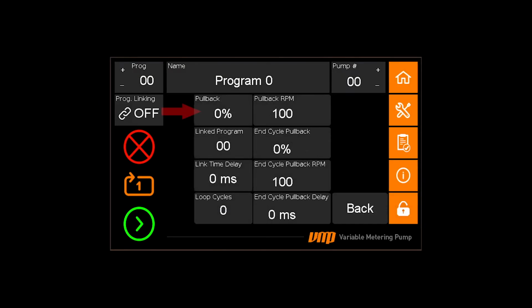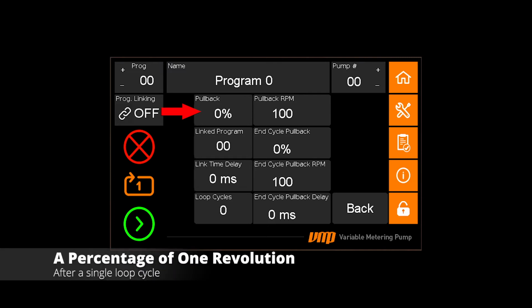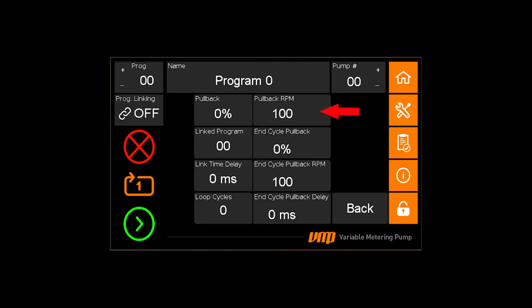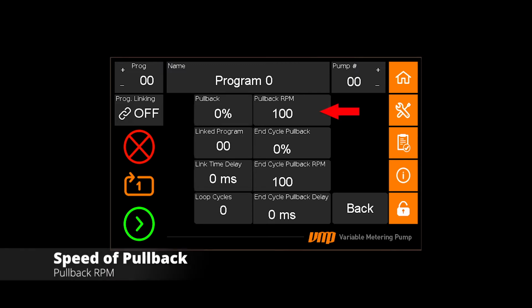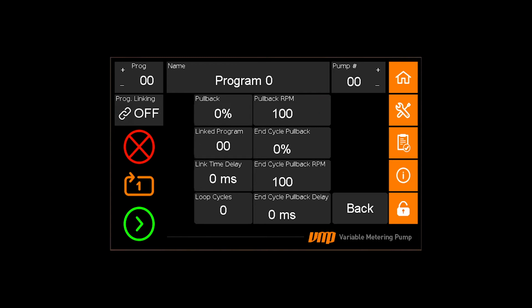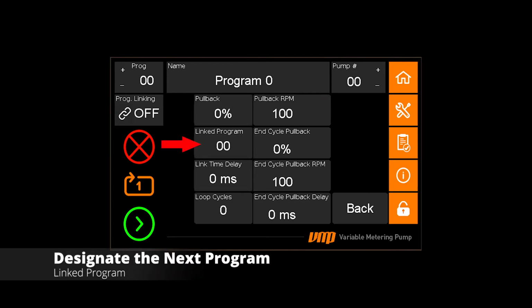First in your top left, you have pullback. This indicates the percentage of 1 revolution the pump will run in reverse after a single loop cycle to pull fluid back into the supply line. Next to that, you have the pullback RPM. This indicates how fast that pullback function will pull the fluid back into the line. Under that, we have the linked program. This indicates the next program that will run after the current program finishes its cycle.